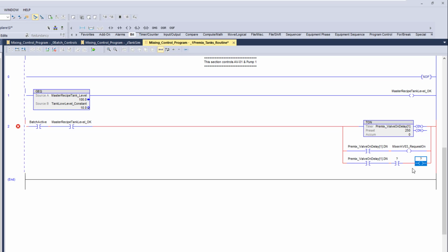So they will be actually sending 120 volts, or it could be DC, right? It could be DC to it, either or, right? That's basically the two common things that are used inside of controls these days, and more or less aiming towards DC. A lot of people are using DC now because it's a lot safer. So this would be just a coil on a solenoid valve, right? Telling the solenoid valve to cut on, and the air would turn it on.